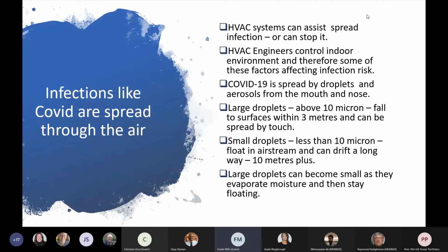We know, as Catherine said, that COVID is spread by droplets and aerosols that leave the mouth and nose and enter the airspace. Large droplets above 10 microns tend to fall locally within the source area. However, the smaller ones are aerosols - they drift along in the airstream, down corridors from one room to another, and can be picked up in the ductwork system and distributed through the HVAC system. Don't forget, large droplets can become small because they evaporate moisture and stay floating in the air.